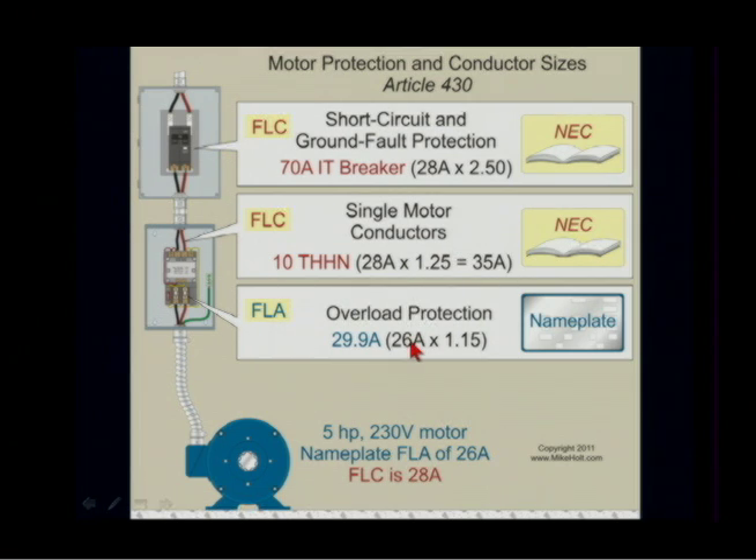You size the overload — the overload device is actually going to be selected by the manufacturer — but the overload calculation would be 26 amps times 1.15, which gives 29.9. And if it were a fuse, which is not in this example, it would be no more than 29.9 amps.